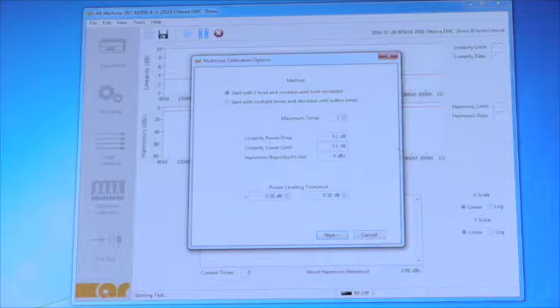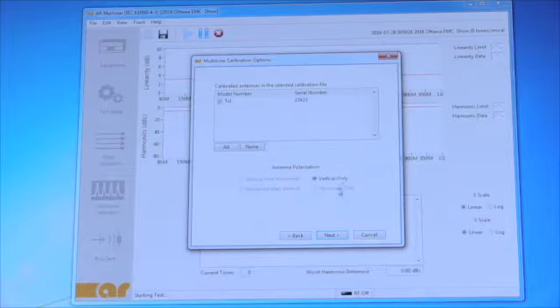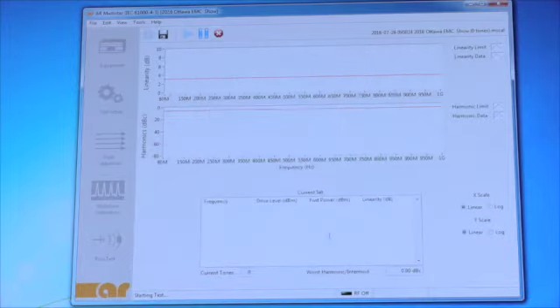So here you can check for 2 dB compression. You can set that limit, and then you can set your harmonic limit to 6 dBc, which we have per the IEC 61000 standard, which defaults. Your power level and tolerance, you set that. Vertical only. This is the antenna you selected. Now you put your test information for calibration again, and you hit run.